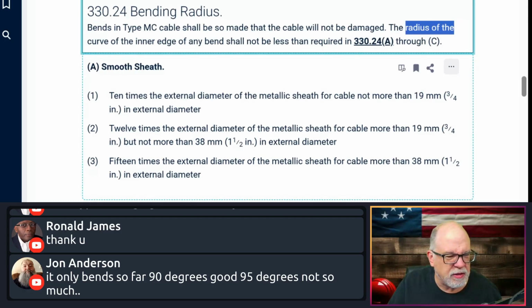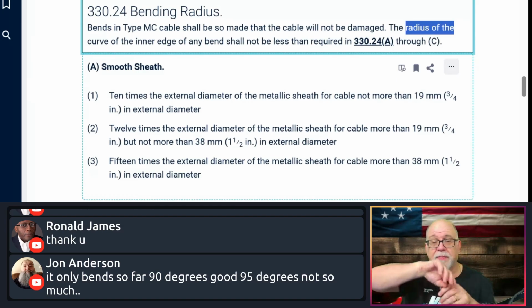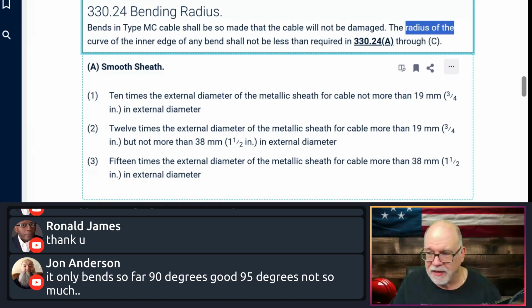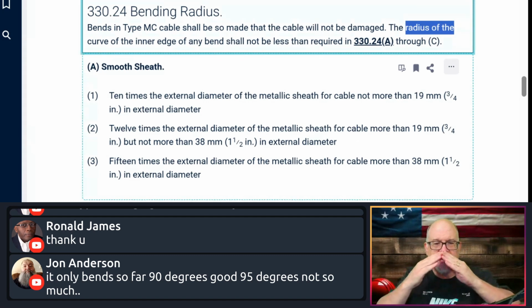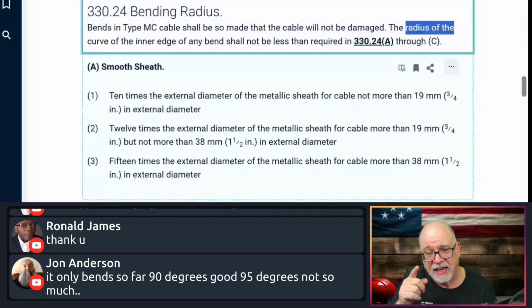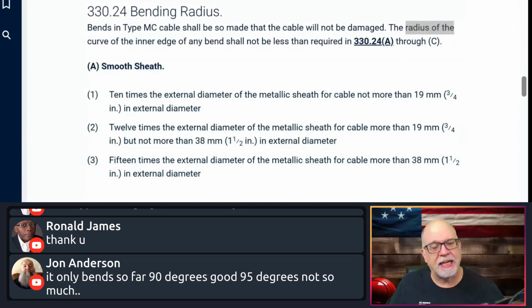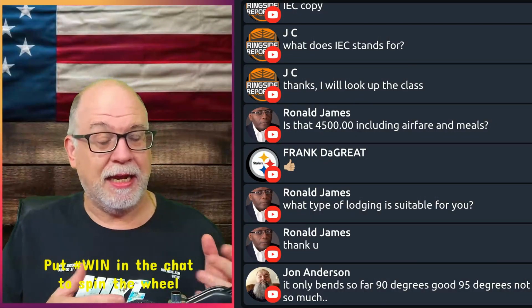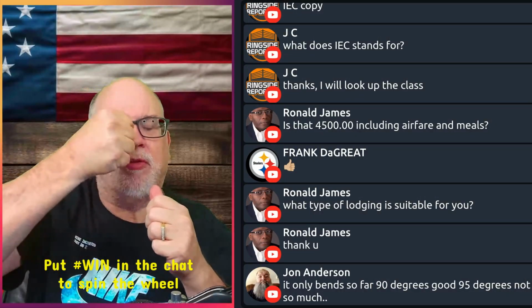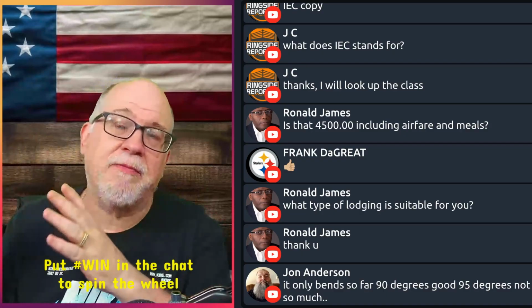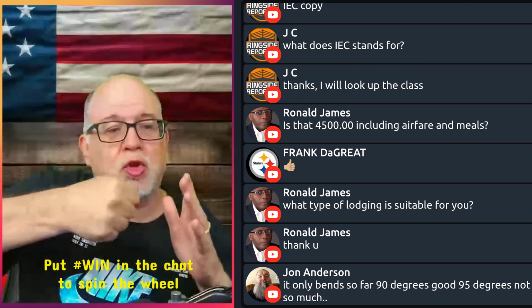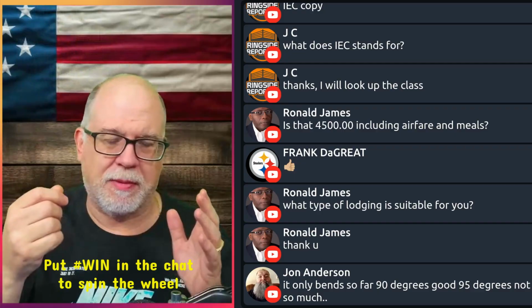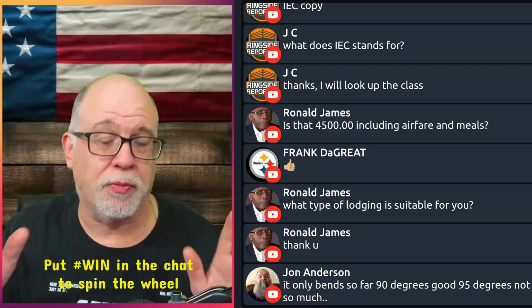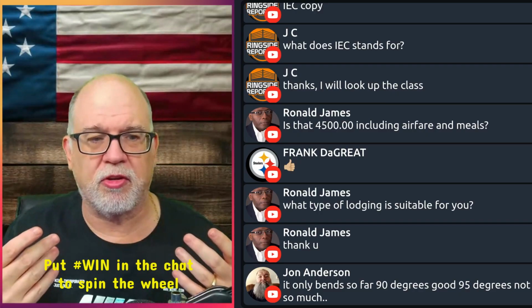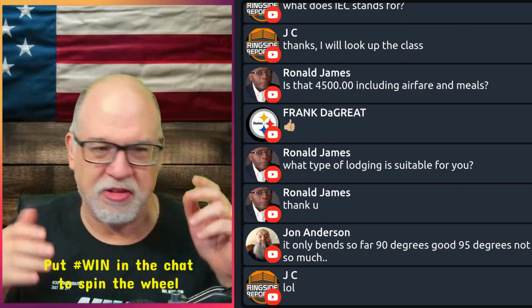John says it's only bent 90 degrees so far, good; 95 degrees, not so much. Yeah, if you start bending it tighter than a 90, you're going to blow out the back end of it, or pop the inside, and the armor could turn into the cable and damage the conductors inside. Thank God it has a wrap binder, because people do some funky things. Where I have seen this become a problem is that people forget it's not non-metallic sheath cable. They come down and try to turn it tight to get it back up into a box, maybe because they came from residential and are just starting to do some MC work, and they want this big loop underneath it. Don't do that. I'd rather you just come straight into the box, okay? Especially no loops on MC cable. It's unnecessary to create loops. It puts undue tension on the cable assembly itself. Just go right to the box. You get me? I'm just saying, okay?